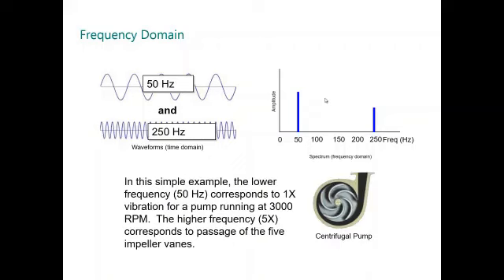In this example, you have a pump and the pump has five vanes. That means this vibration is related with the vane pass frequency.